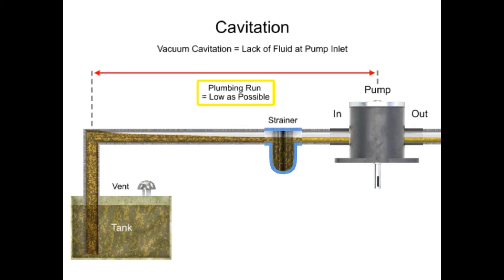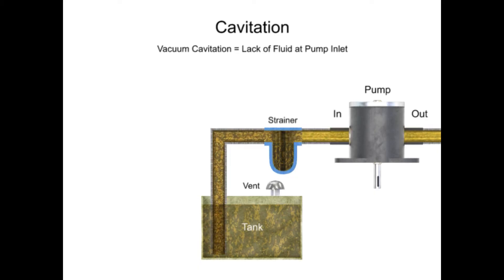Additional causes include too long a plumbing run, restricted or collapsed plumbing hoses, or too viscous a fluid, such as when the temperature drops and oil thickens.